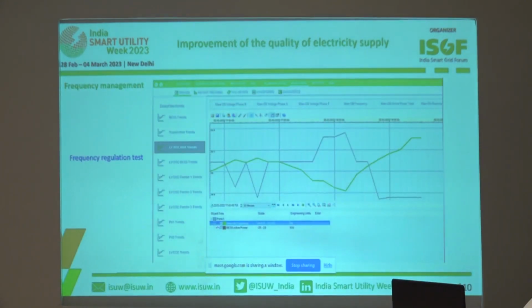We have also tried a frequency regulation test with the battery. In the dark curve you have the power, and in green the main frequency. When the frequency drops, the battery injects power, and the opposite, when the frequency is too high, the battery is loading. It was just a test because the battery is a little bit too small to have a real large effect, but in any case it was working quite well.